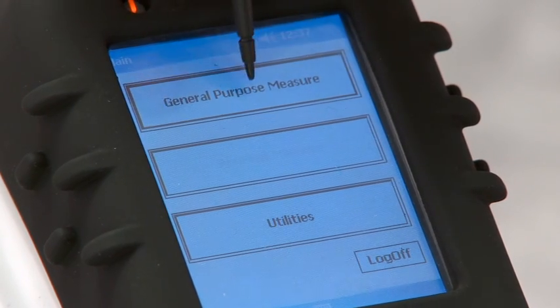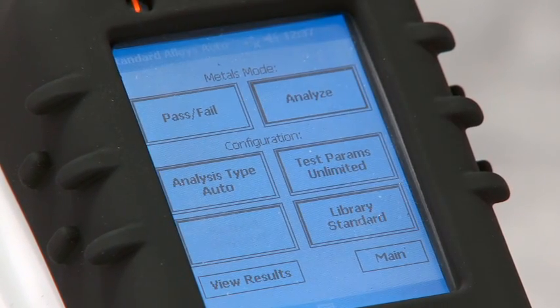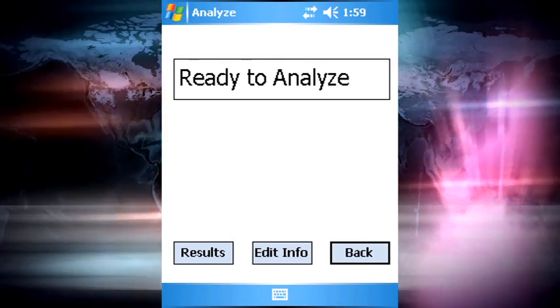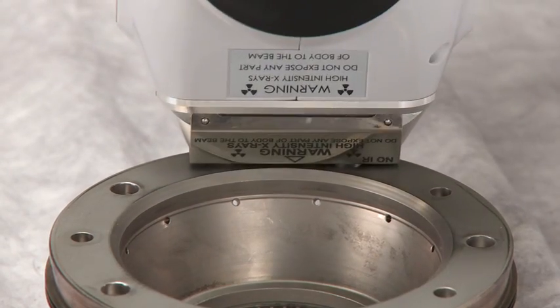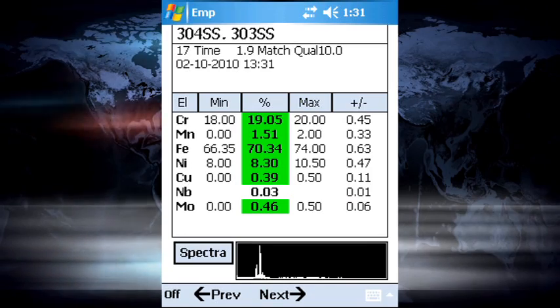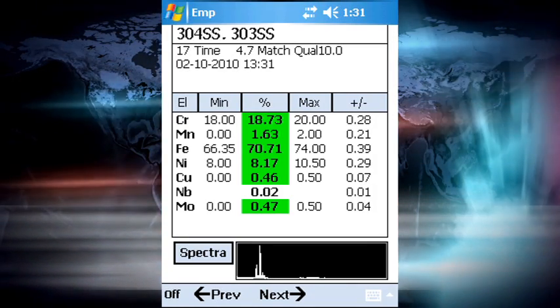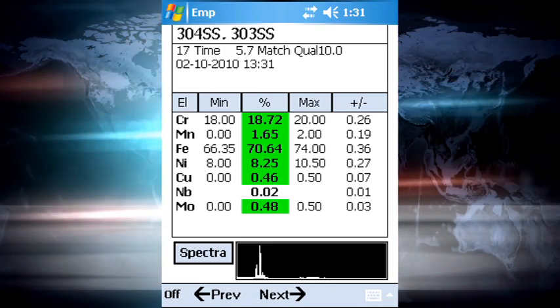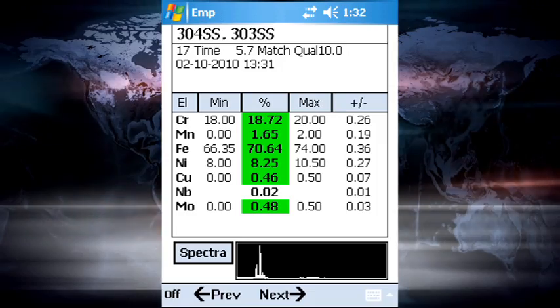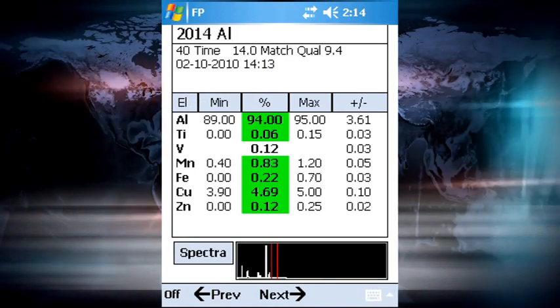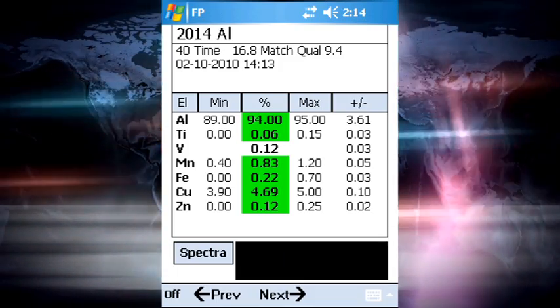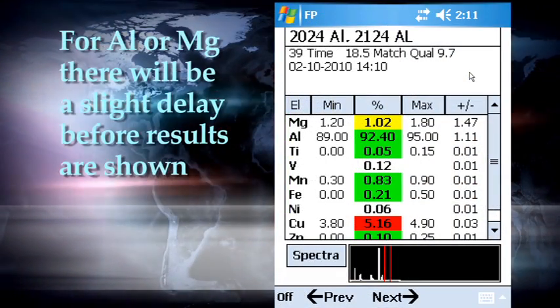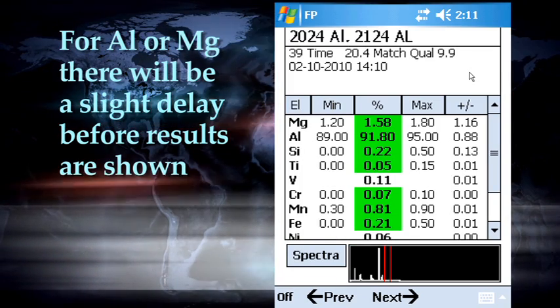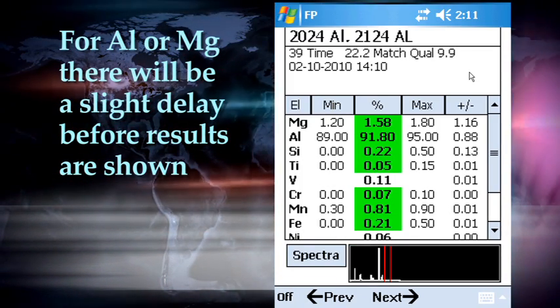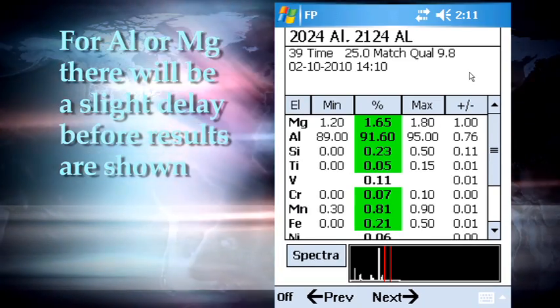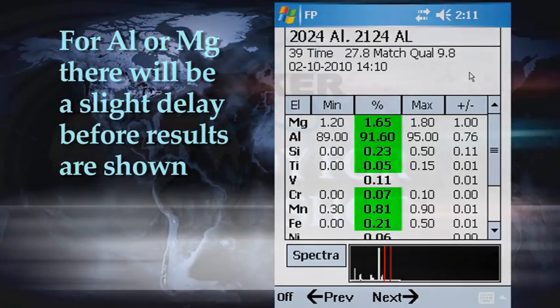The S1 software supports an automatic calibration selection mode known as universal mode. When the analysis is started in universal mode, the software determines the most appropriate calibration to use. If the sample falls within the boundaries of the empirical calibration, the appropriate empirical calibration will be used, and the light elements will be determined. If the alloy falls outside of the range of empirical calibration, the appropriate fundamental parameters method will be selected. In the case where the alloy is predetermined to be a light metal, that is aluminum or magnesium, there will be a slight additional delay at the beginning of the measurement, as the data acquisition conditions will be changed and the measurement restarted.